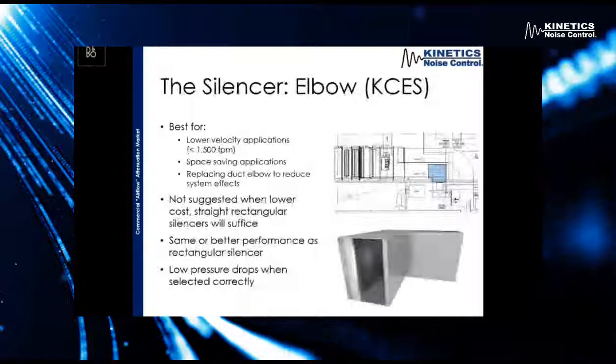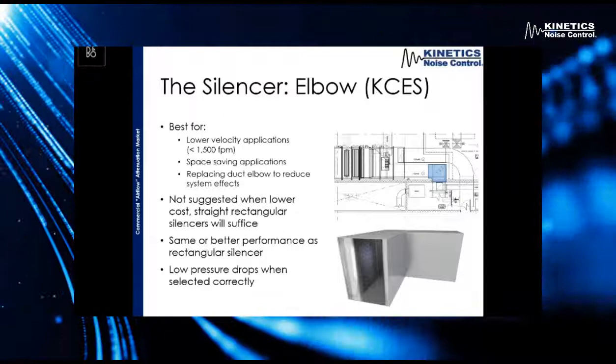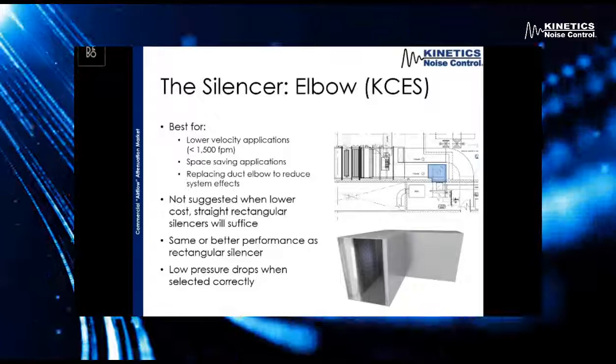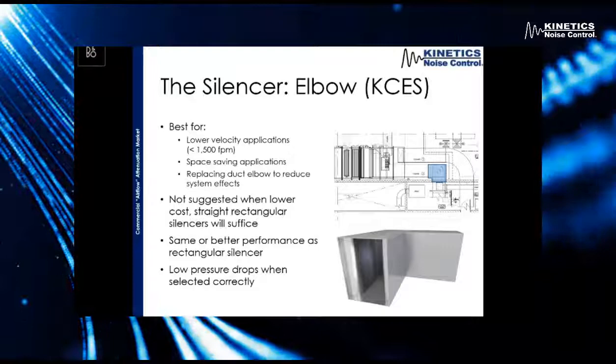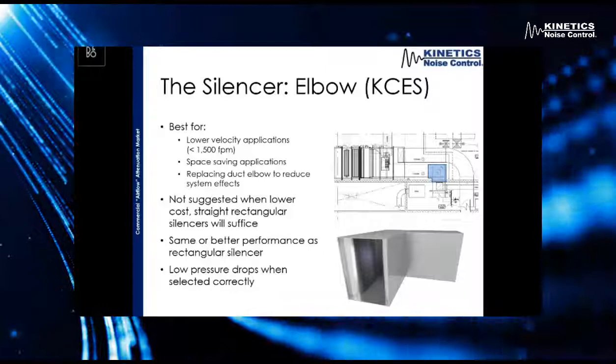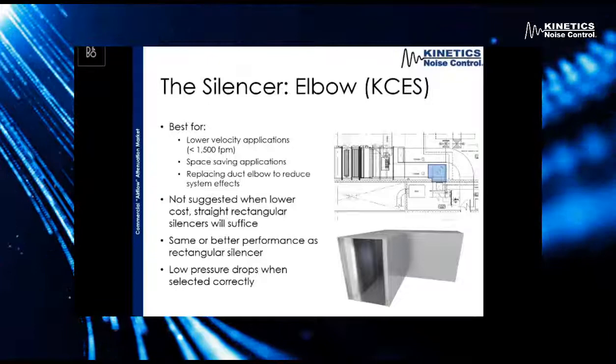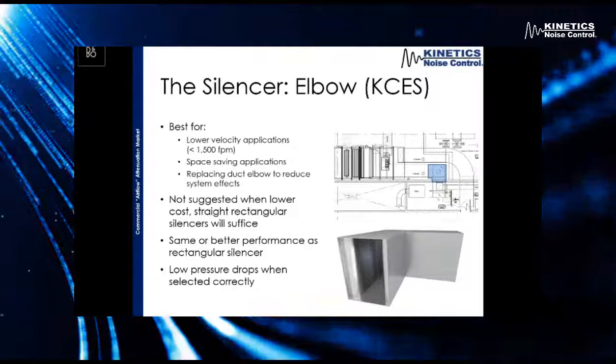Next, we have an elbow silencer. We generally suggest these when a rectangular silencer just won't work, usually due to a space constraint or a poor system effect condition. As you can see in the image on the right, we don't have a lot of room in that mechanical room for a rectangular silencer. This is an application where an elbow silencer really works — generally we can get the same or better performance with an elbow silencer versus a rectangular one. We just have to make some considerations for the pressure drop. They are better suited for lower velocity applications, usually around 1,500 feet per minute or less. Sometimes we'll have a system with two mitered elbows and a rectangular silencer between them — that's a really poor system effect condition. In that case, we would replace one of those mitered elbows with an elbow silencer, which improves the overall system effects.